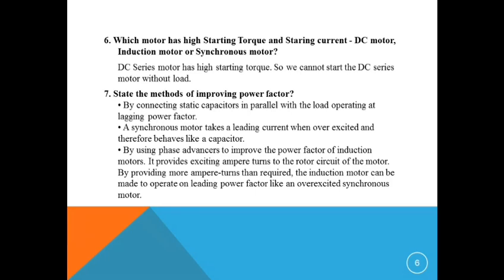By using phase advancers to improve the power factor of induction motors, which provide exciting ampere turns to the rotor circuit of the motor. By providing more ampere turns than required, the induction motor can be made to operate on leading power factor like an overexcited synchronous motor.